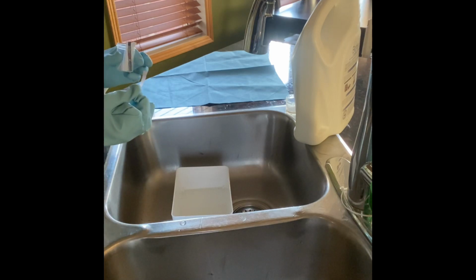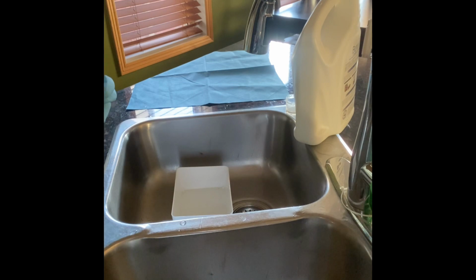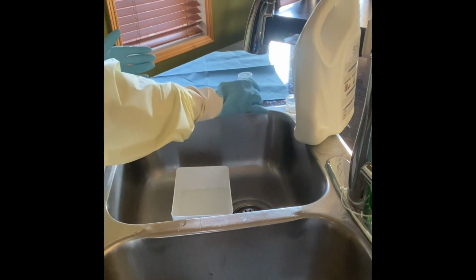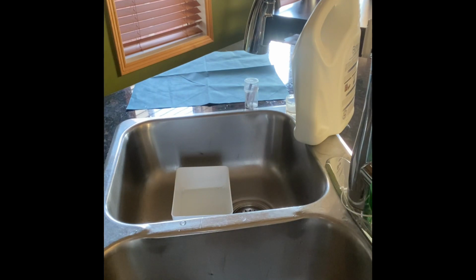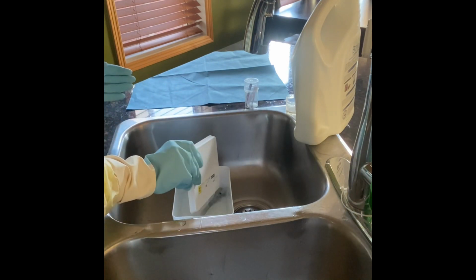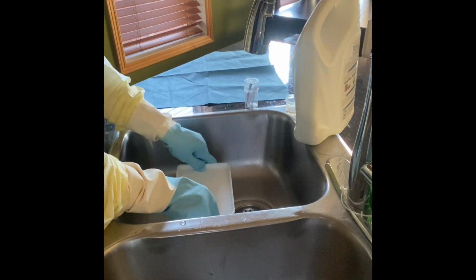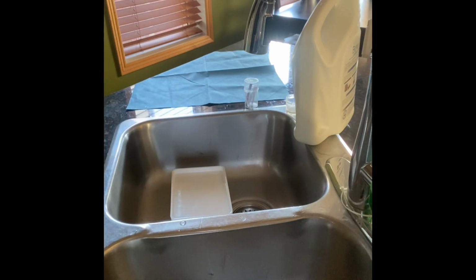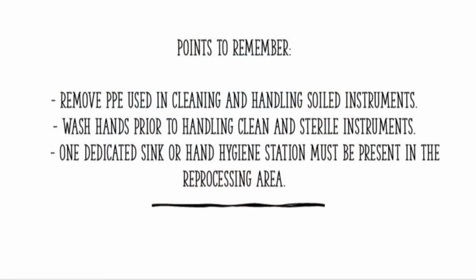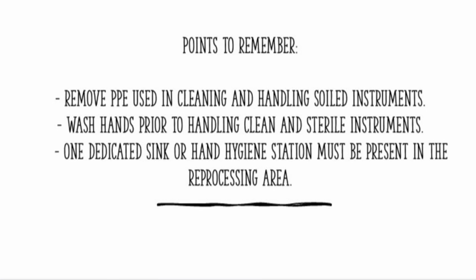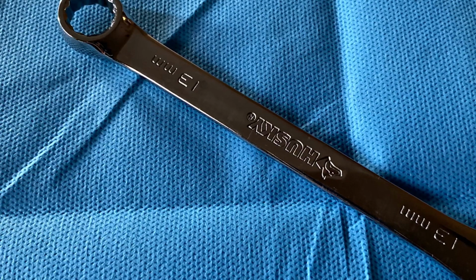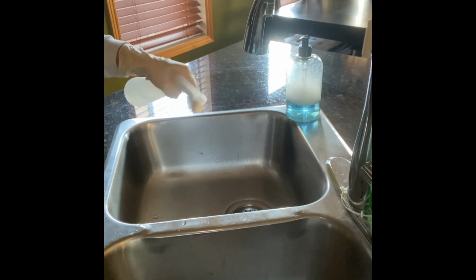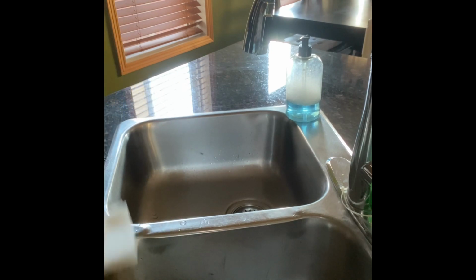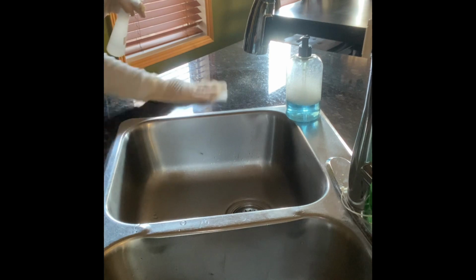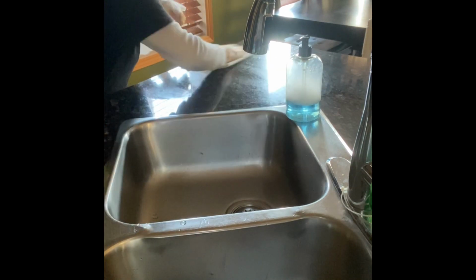All logs and documentation forms should be recorded. Devices are completely immersed in glutaraldehyde solutions for the recommended time, and then rinse the equipment. Dry the utensils with a clean, lint-free, soft absorbent towel and move to storage of clean area. Disinfect counter space and sink. Dispose of equipment used, doff PPE, and wash your hands. Do not use the reprocessed sink for hand hygiene.